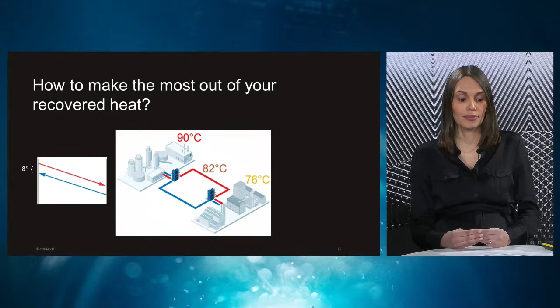To estimate the type of savings that we can get from a waste heat recovery system, we have developed calculator tools. And what you see on the screen now is the results page from such a calculator. Here I have used an example where I've inputted figures for an industry with waste heat available at 90 degrees Celsius, where it's to be cooled down to 50 degrees Celsius. They are now reusing this heat for some other heating purpose, and thereby they avoid using steam that would otherwise be produced by a natural gas-fired boiler.